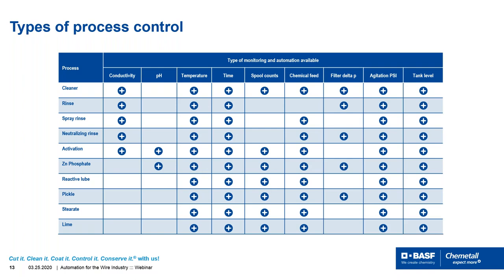Do we want to monitor the chemical feed to know how much went in, how much chemical we used on any given day? If we're looking to do a filter on it, can we monitor the delta P of the filter so we can automatically tell, hey, we need to change this out, or the media is shot, or the pump isn't pumping the way it should? Along with that, the agitation pressure.